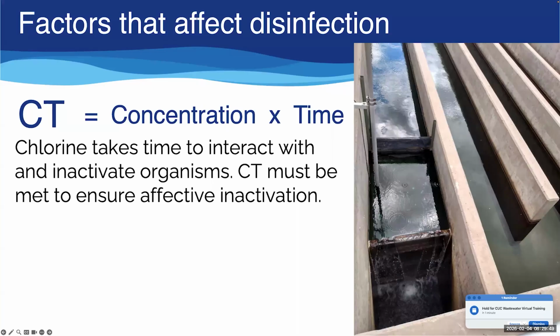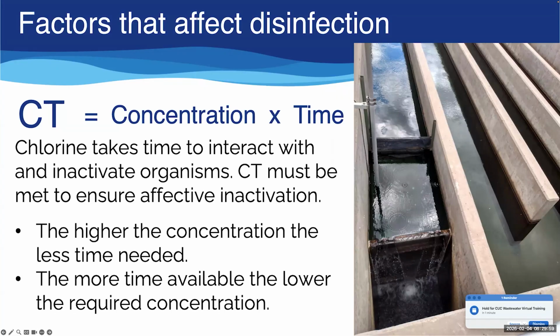Your plant will be designed for a specific amount of chlorine and a specific contact time under specific conditions. So again, that's a really important thing to understand. The higher the concentration of chlorine, the less time you need. The more time you have, the lower concentration you need.